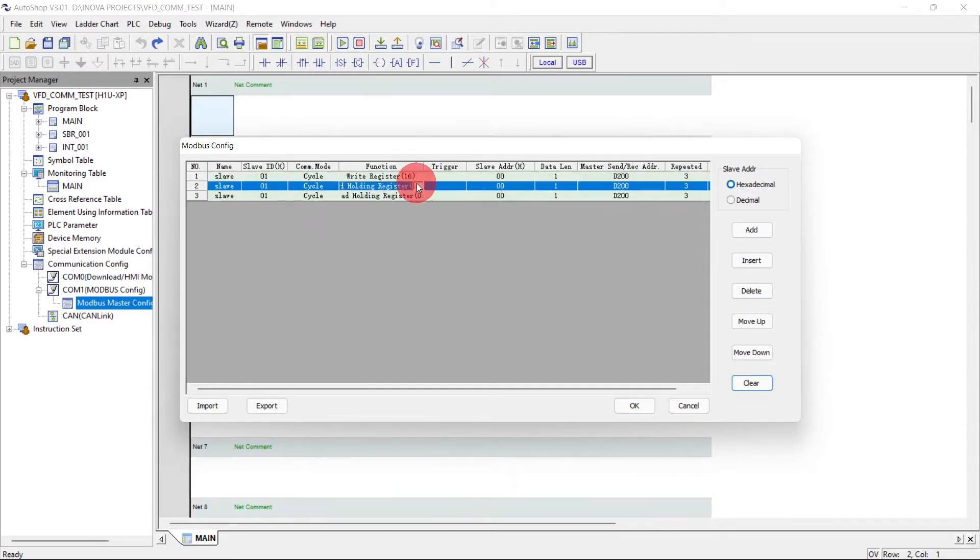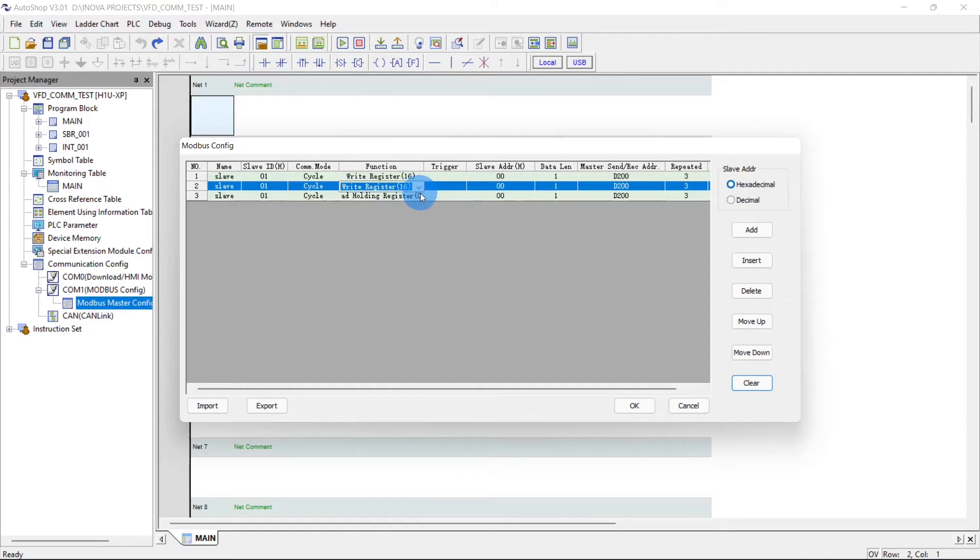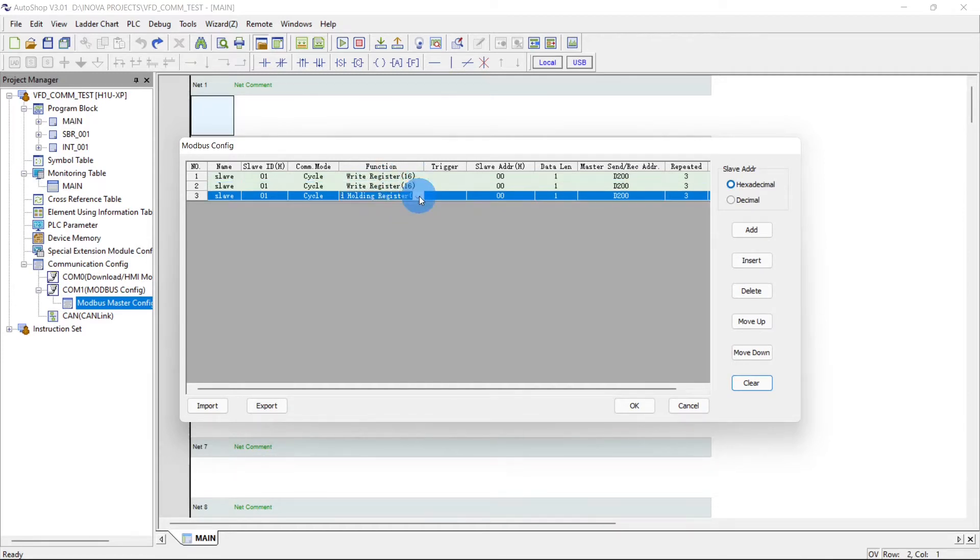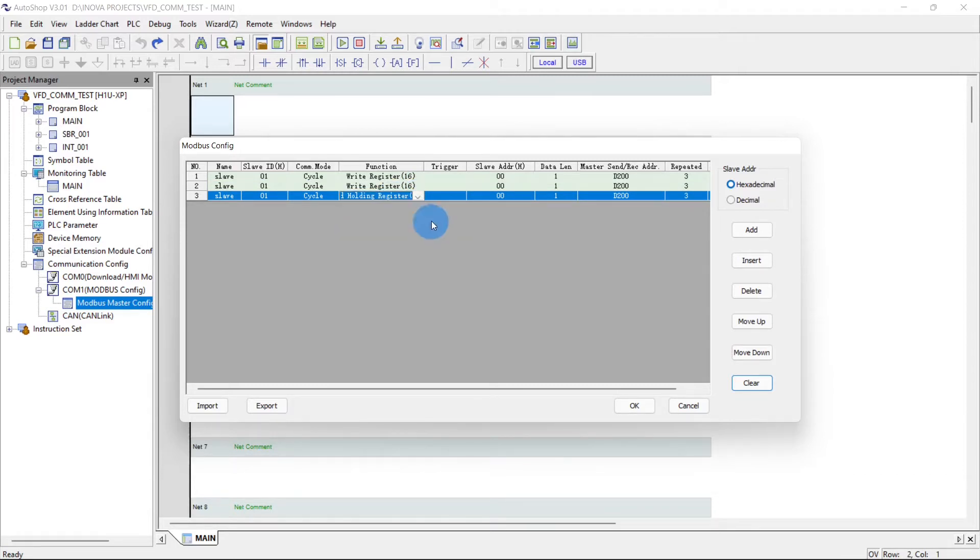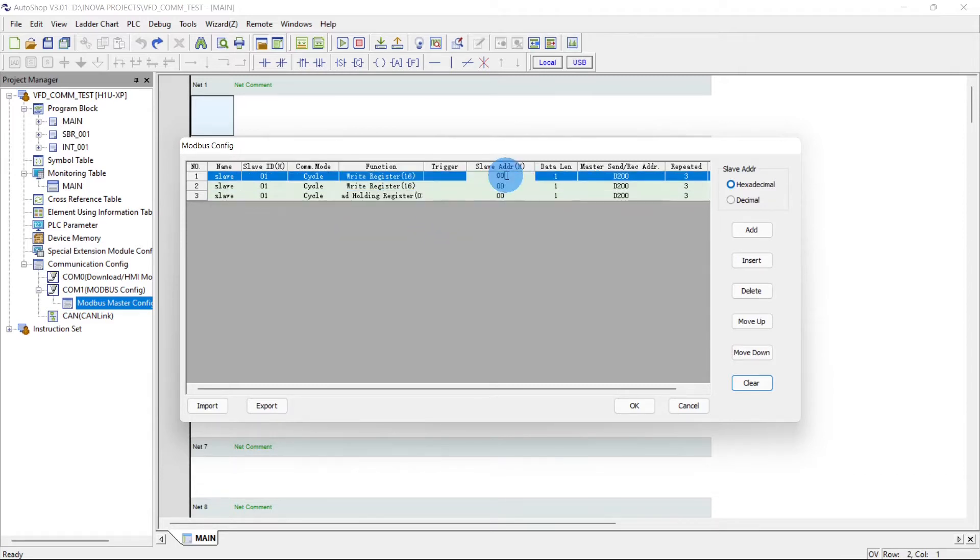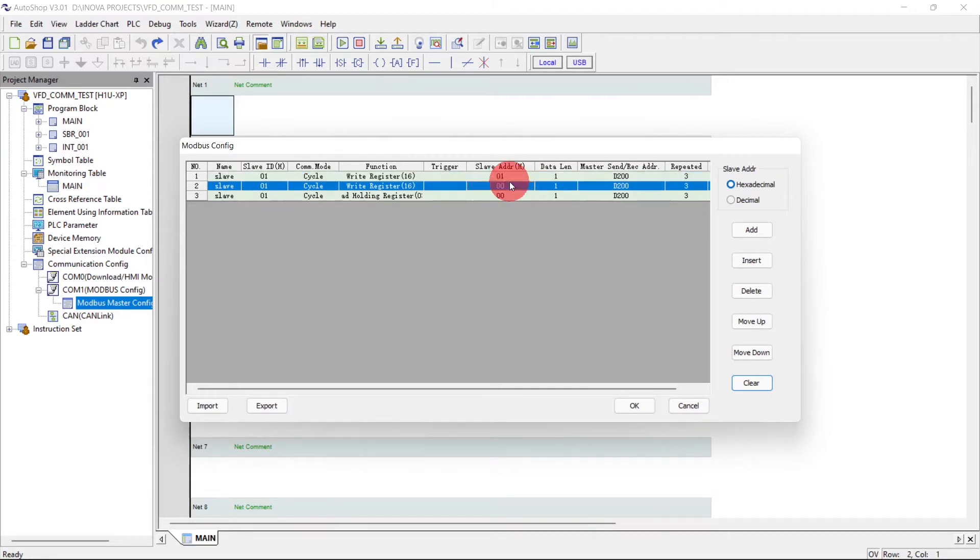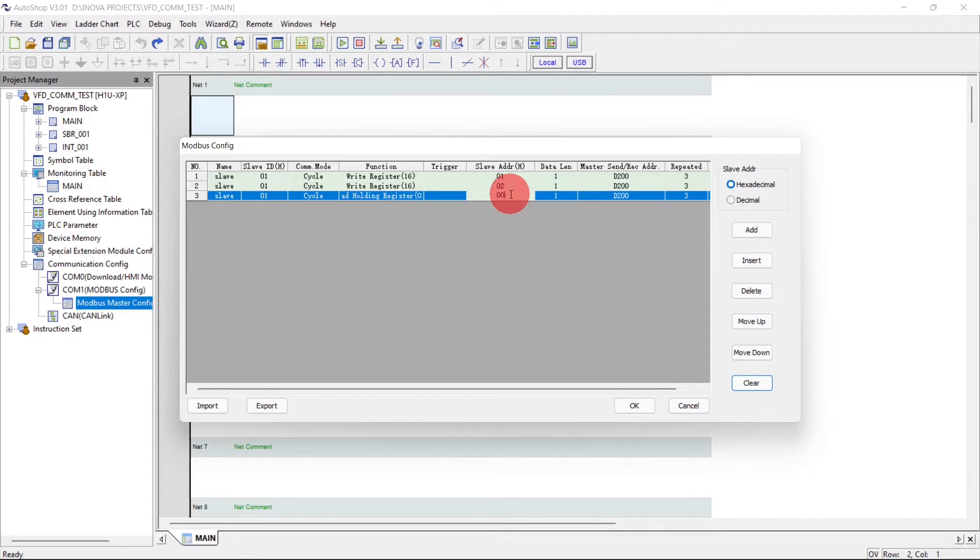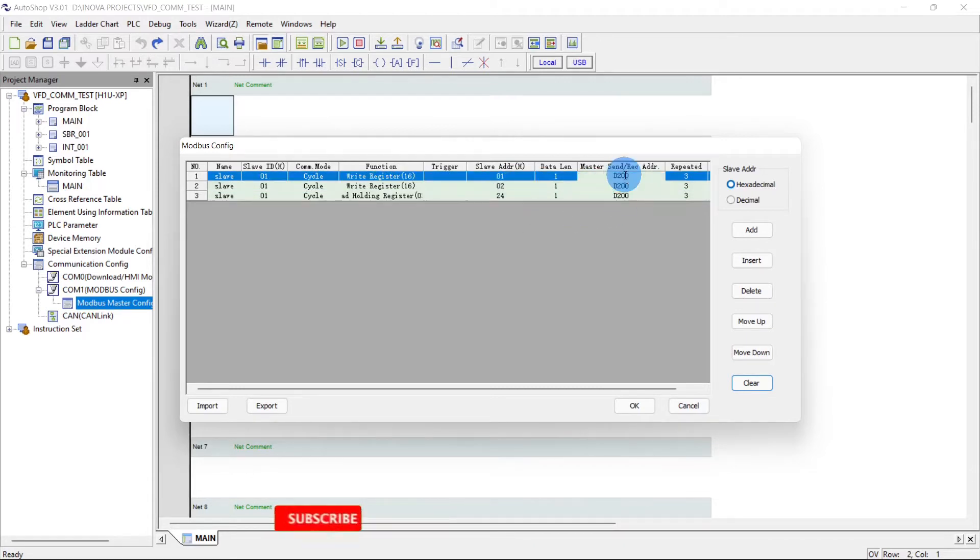Now we have to set the function. This is the write register run command and this is the frequency write, and this will be the read address frequency read. Now the slave address, this is 1 for start, 2 for frequency, and 24 for output frequency read.